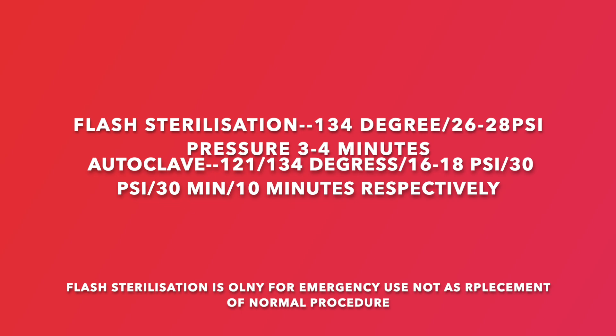So in the last video I discussed with you one of the methods of sterilization, that is steam under pressure, and what we discussed in the last was mainly the autoclave. This autoclave is basically the method of sterilization in which we use steam under high pressure and high temperature. The main purpose of increasing the pressure of the machine or autoclave is to increase the temperature of the steam, to increase the penetrative power of the steam.